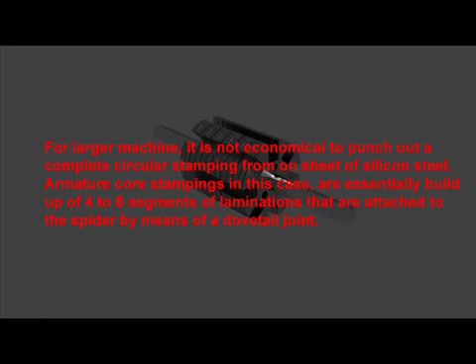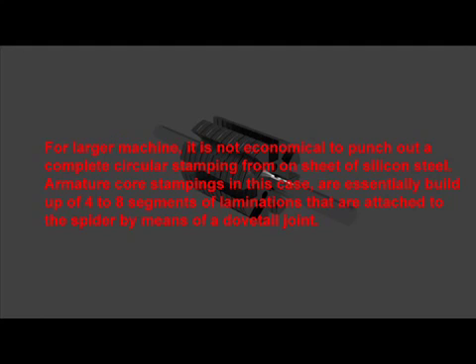For larger machines, it is not economical to punch out a complete circular stamping on sheet of silicon steel. Armature core stampings in this case are essentially built up of 4 to 8 segments of laminations that are attached to the spider by means of a dovetail joint.